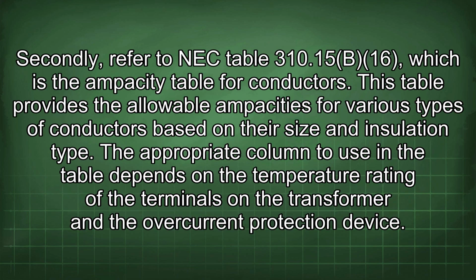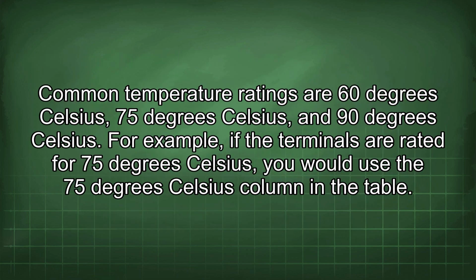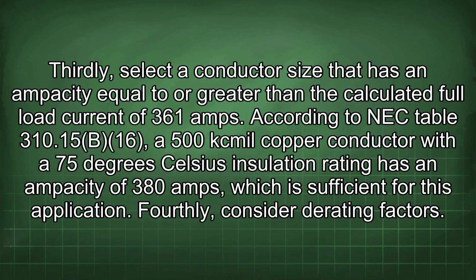Secondly, refer to NEC table 310.15(B)(16), which is the ampacity table for conductors. This table provides the allowable ampacities for various types of conductors based on their size and insulation type. The appropriate column to use in the table depends on the temperature rating of the terminals on the transformer and the overcurrent protection device. Common temperature ratings are 60 degrees Celsius, 75 degrees Celsius, and 90 degrees Celsius. For example, if the terminals are rated for 75 degrees Celsius, you would use the 75 degrees Celsius column in the table.